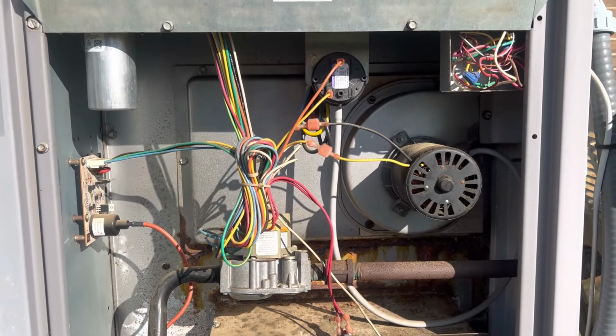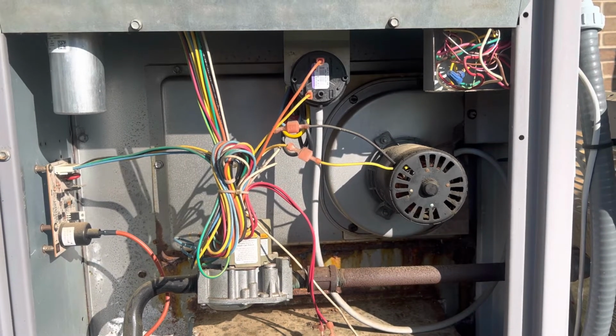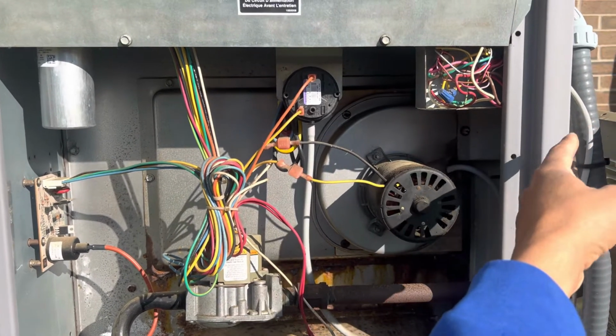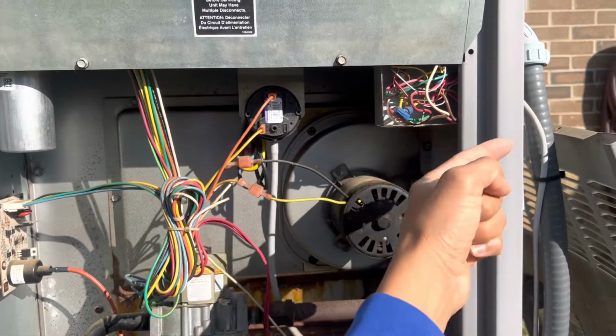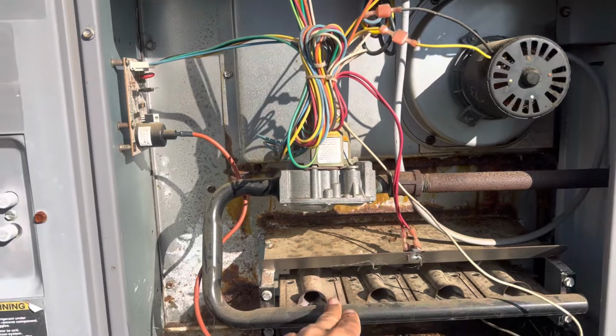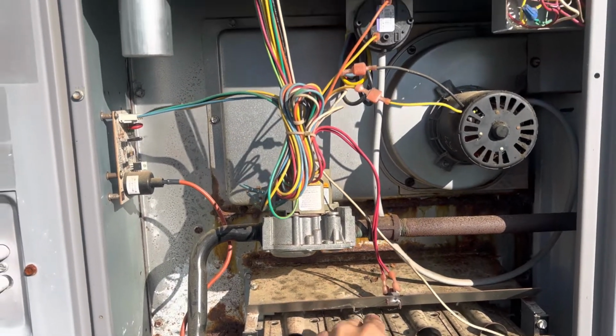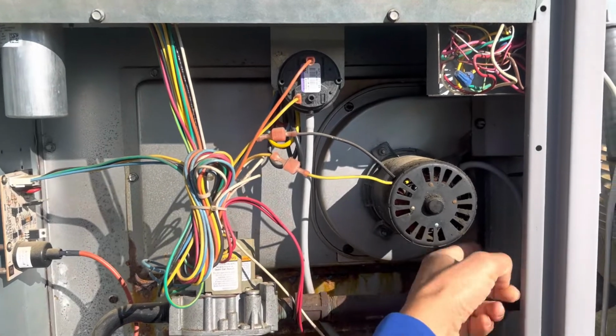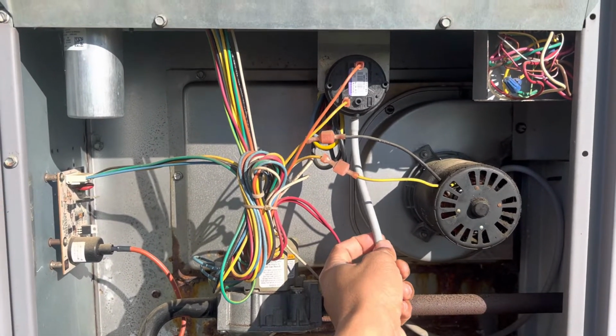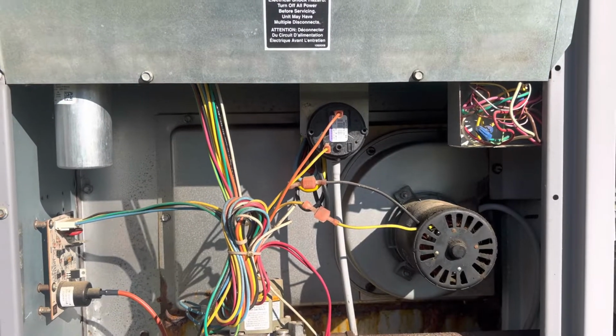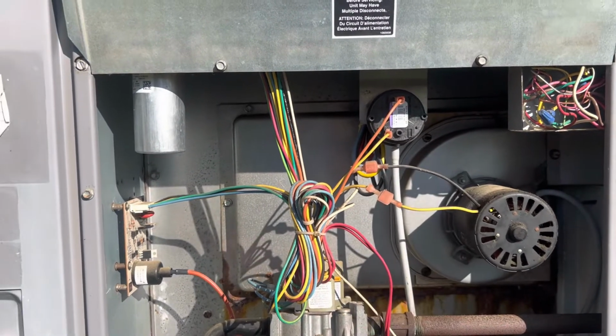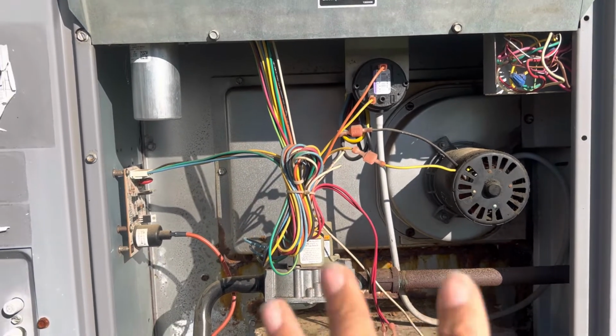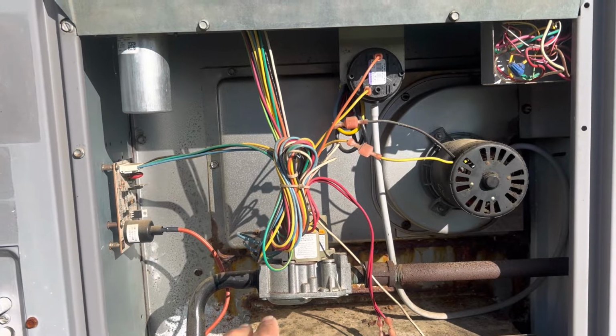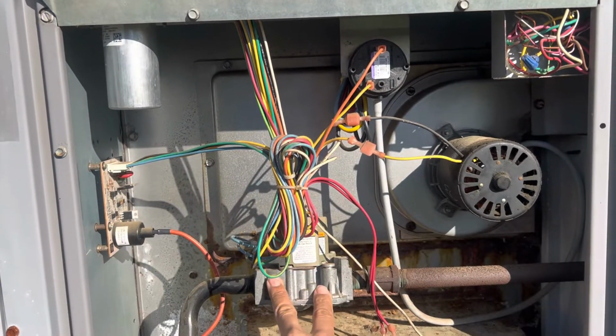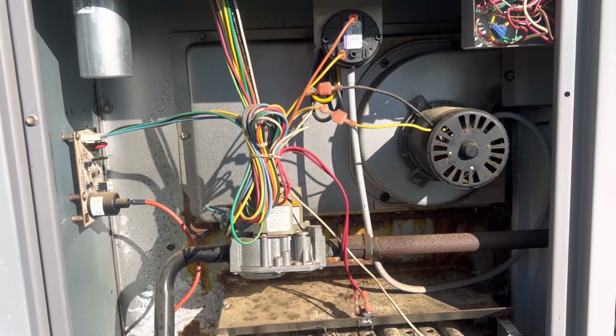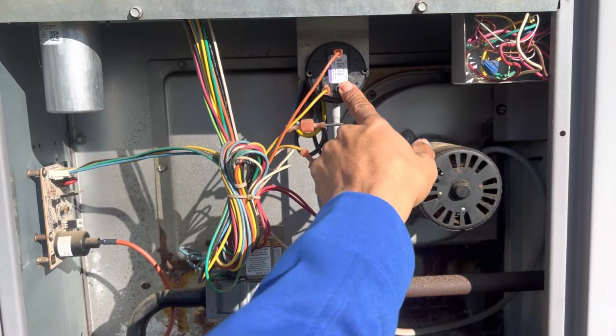First thing that happens in a furnace, the vent motor comes on. It's gonna pull a draft through that heat exchanger. So the vent motor is gonna suck air out through the exhaust, which is gonna cause air to go in through this way, right? The vent motor comes on, also causes a suction down this tube, which closes this pressure switch. When that pressure switch closes, that tells the board that the vent motor is on. So once that pressure switch closes, now it is safe to release gas, okay? Vent motor, pressure switch closes.